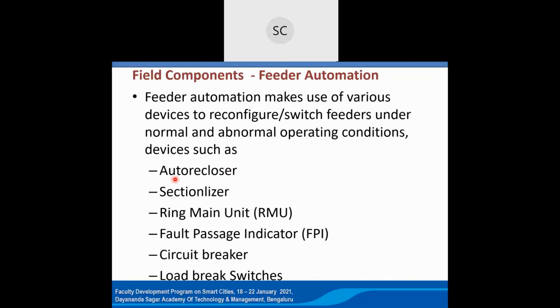And the auto recloser concept is more or less breaker kind of thing; I will come to the details in a later slide. Then coming to the sectionalizer. A sectionalizer is an element similar to a load break switch. It is not like a breaker and it cannot handle fault current. But whenever a fault happens, it gets tripped. Again, in the fault current, we cannot energize it remotely. So this sectionalizer isolates where the fault happens. Once the fault is cleared, then we can energize the sectionalizer remotely. So the functionality of the sectionalizer is to isolate the faulty area, so that when any fault happens, only a very small area is affected. So the number of customers affected will be less by adopting this feeder automation system.